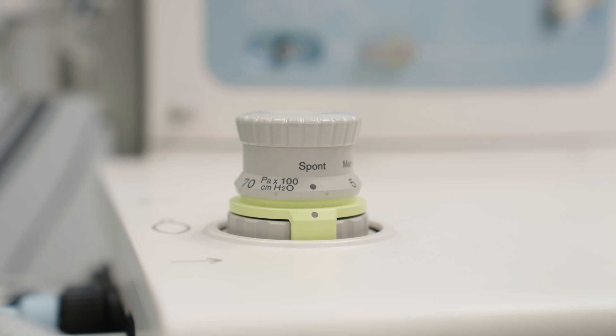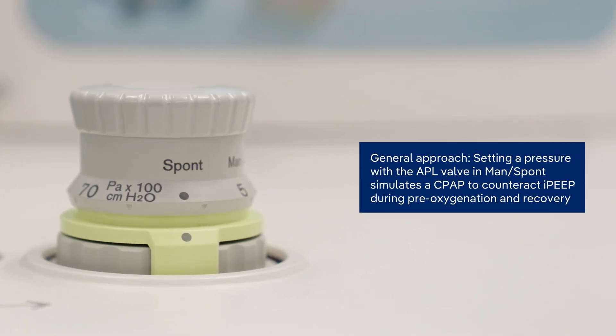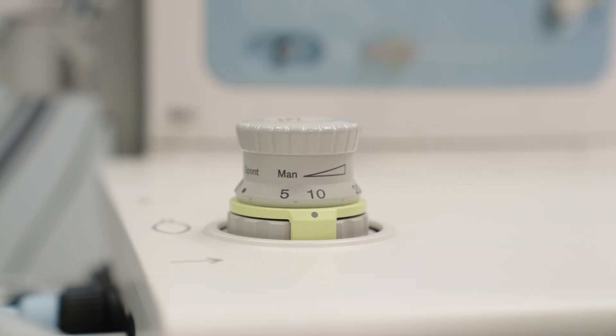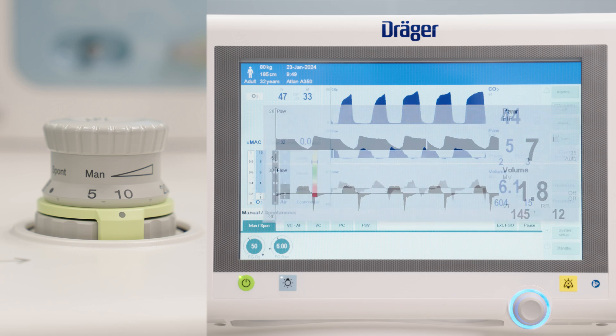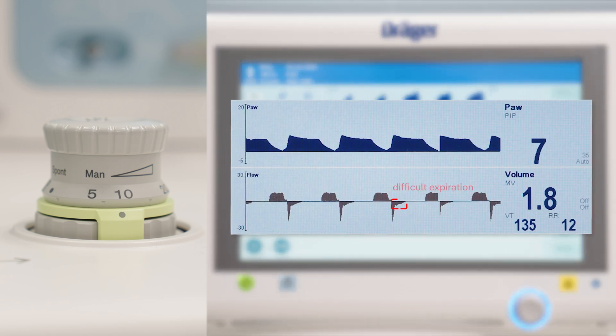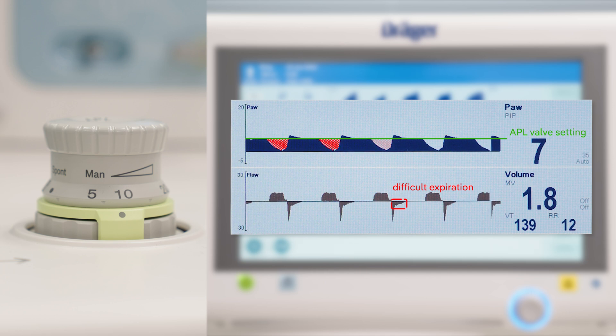In practice, the APL valve is used to simulate a CPAP pressure in manual spontaneous mode to counteract the intrinsic PEEP of obese patients during pre-oxygenation and recovery. However, the set APL valve pressure acts more as a resistance and hence does not reduce the work of breathing and merely makes expiration more difficult. Furthermore, the spontaneous breathing of the patient typically creates a pressure drop and pressure is not maintained at a constant level.